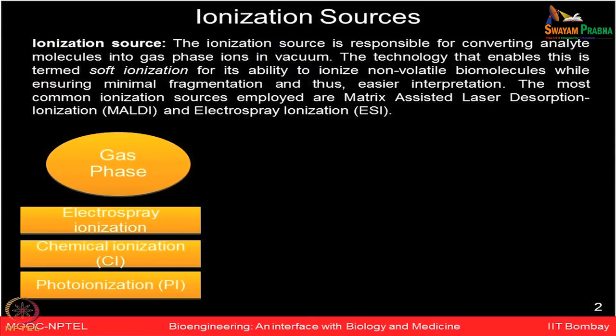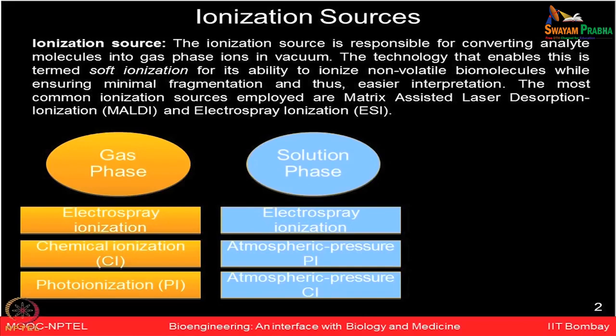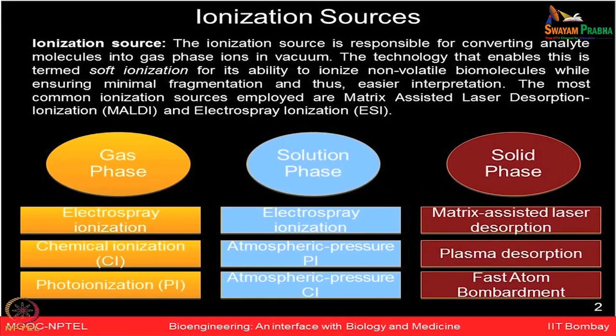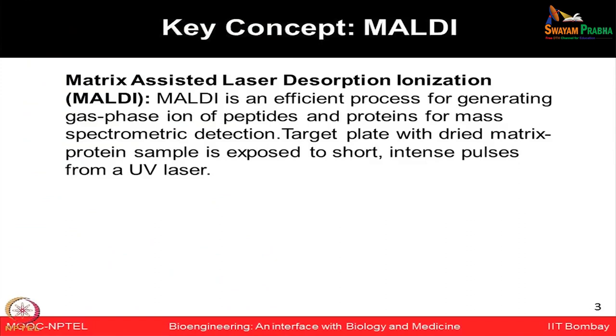The first component of the mass spectrometer is the ionization source. Soft ionization is known for its ability to ionize non-volatile biomolecules while ensuring minimal fragmentation, so one can easily interpret the data. The most commonly used ionization methods include electrospray ionization (ESI) and matrix-assisted laser desorption ionization (MALDI). MALDI is one of the efficient processes for generating gas-phase ions of peptides and proteins for mass spectrometry detection.